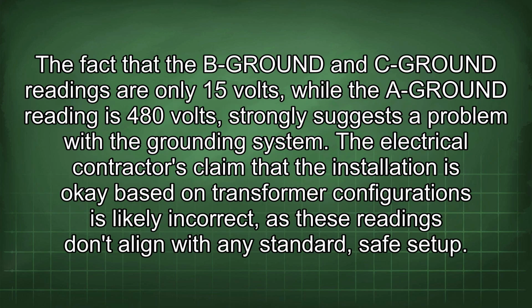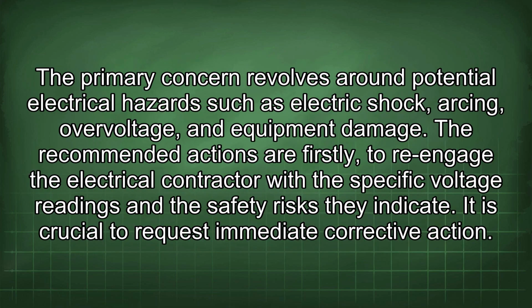The fact that the B ground and C ground readings are only 15 volts, while the A-ground reading is 480 volts, strongly suggests a problem with the grounding system. The electrical contractors' claim that the installation is okay based on transformer configurations is likely incorrect, as these readings don't align with any standard, safe setup. The primary concern revolves around potential electrical hazards such as electric shock, arcing, overvoltage, and equipment damage.